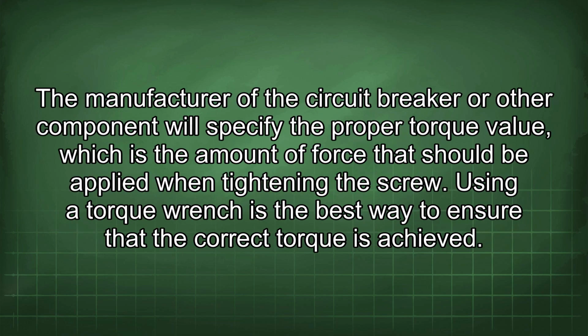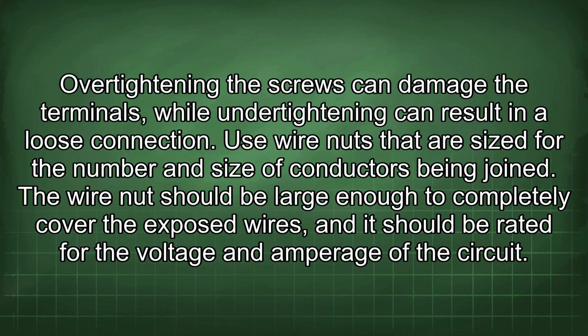The manufacturer of the circuit breaker or other component will specify the proper torque value, which is the amount of force that should be applied when tightening the screw. Using a torque wrench is the best way to ensure that the correct torque is achieved. Over-tightening the screws can damage the terminals, while under-tightening can result in a loose connection.